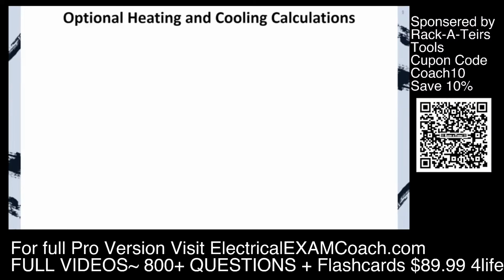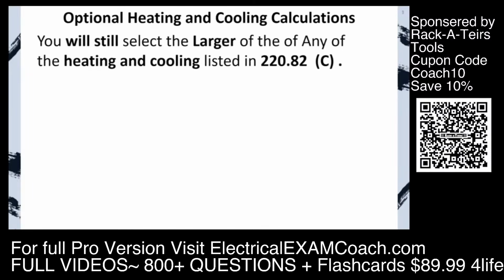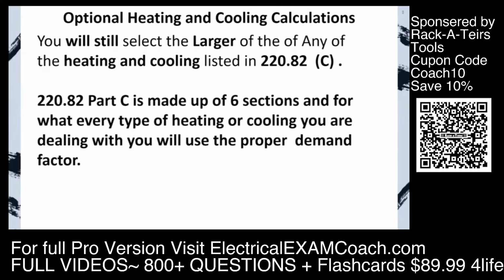With the heating and cooling optional method, we still will choose the larger of any 2 of the heating and cooling listed in 220.82c. It's very simple. If you get an optional method whole house or an optional method heating or cooling, you just go down and read the prescription for each part. There are 6 different parts. It tells you what to do. It's very simple and easy to understand. And then once you've calculated the heating and the cooling, you just select the larger of the 2.